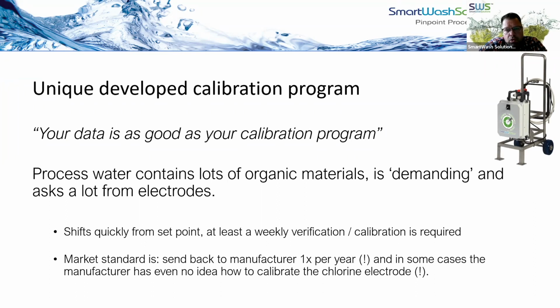But if you do not calibrate your sensors, how reliable is your data then? Your data is as good as your calibration program is. So we have developed our own calibration program to calibrate the chlorine sensor. We know chlorine sensors are tricky and difficult to calibrate, but we have found a method, and I think that's the only way to do it.